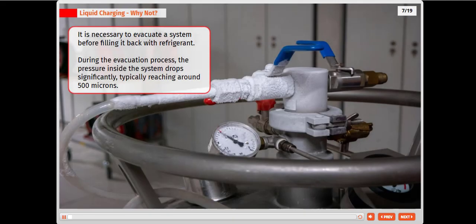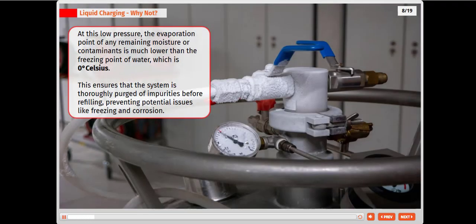It is necessary to evacuate a system before filling it back with refrigerant. During the evacuation process, the pressure inside the system drops significantly, typically reaching around 500 microns. At this low pressure, the evaporation point of any remaining moisture or contaminants is much lower than the freezing point of water, which is 0 degrees Celsius. This ensures that the system is thoroughly purged of impurities before refilling, preventing potential issues like freezing and corrosion.